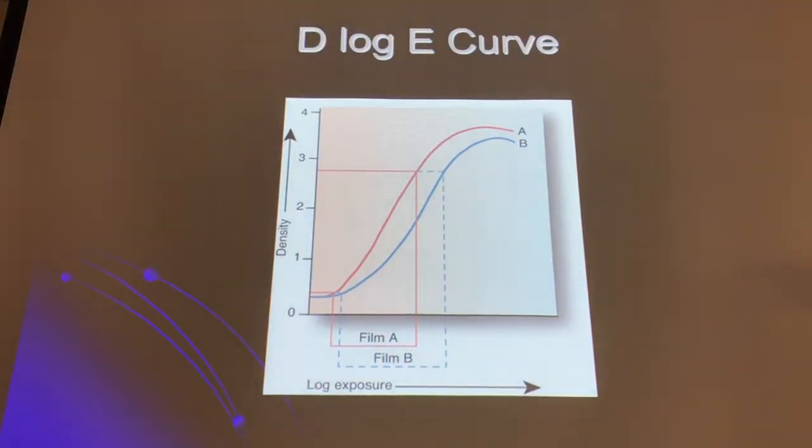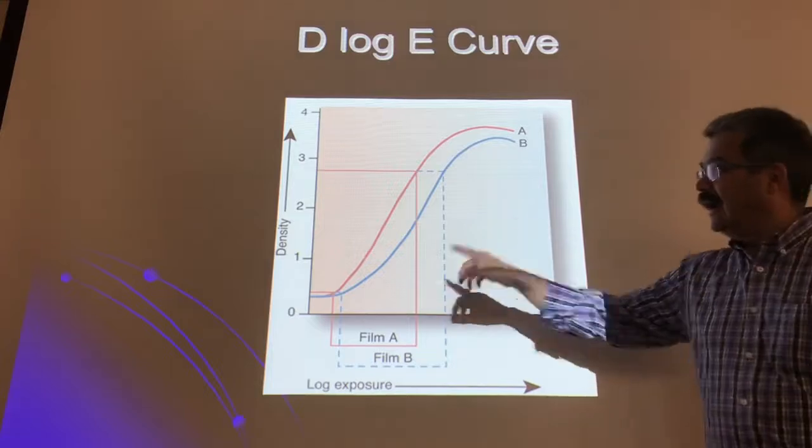Now, why would a hand look dark? If at some time we use 1.6 mAs, but you can see it's a high contrast hand, if it's just an X-ray of a hand. Why wouldn't it have darker shades on that graph? Because your algorithm has been designed to work that way. Your algorithm has been set so that if you use that value, you're going to have a high contrast image. If it was film, you would have to use a film that works like that.